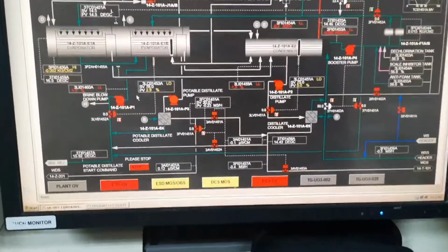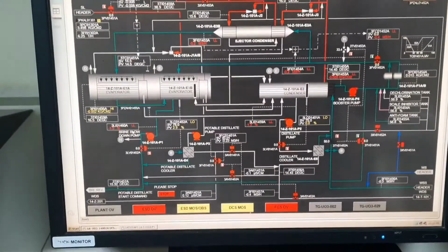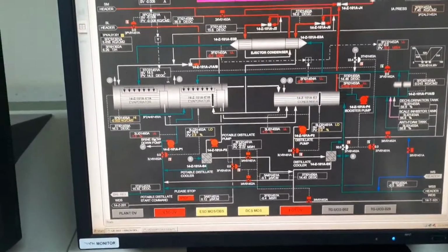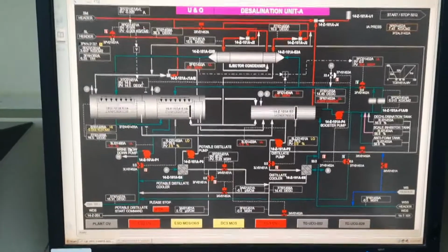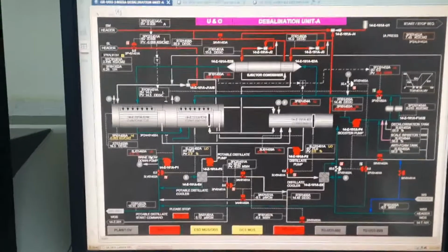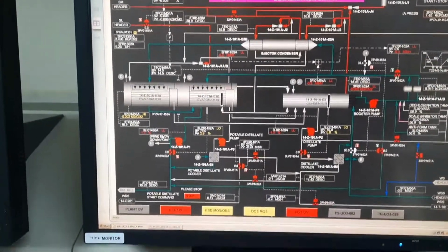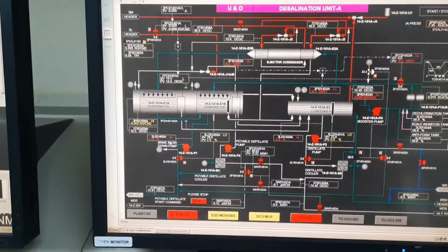So when you dose the acid, the acid continues circulating, and inform the laboratory to check the pH, the concentration, and the EDTA content, how much. How many liters of injection? First you dose 1 meter cube, and after every 1 hour we need to check the pH.